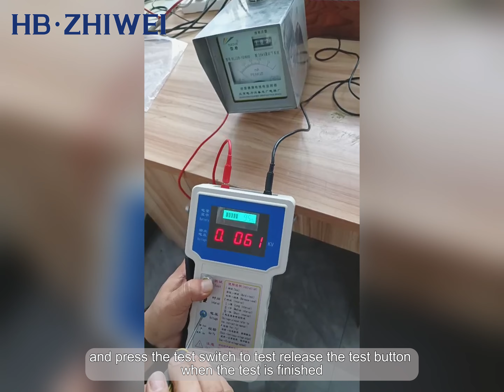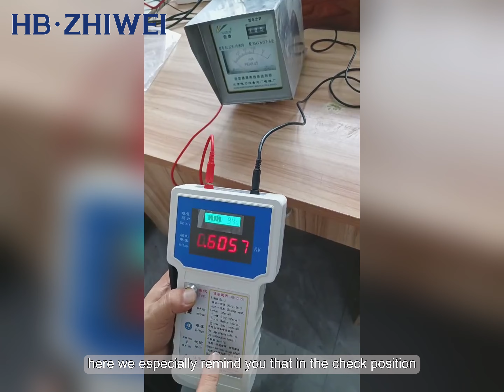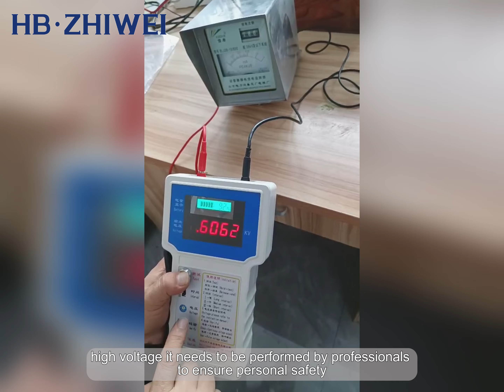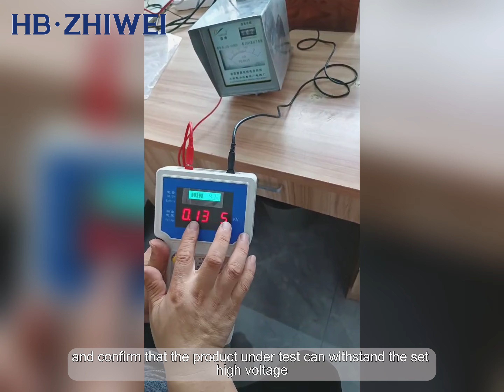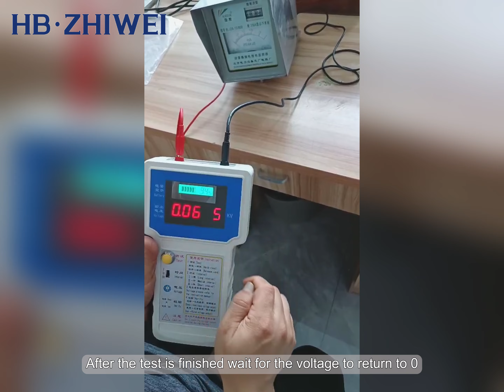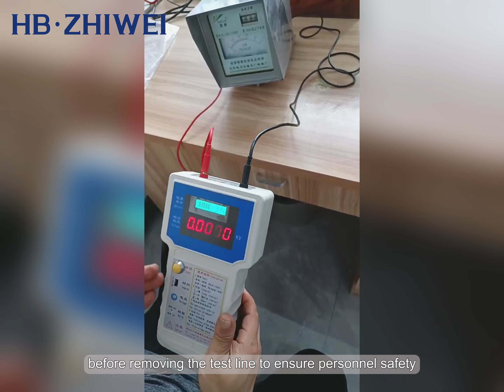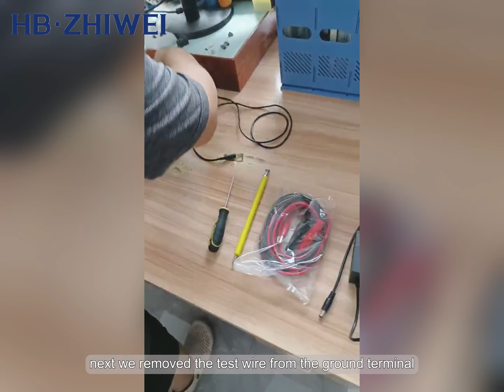Customers can choose the appropriate voltage level for testing according to their test needs. We will not demonstrate them one by one here. Here we especially remind you that in the check position, the instrument will continue to output the set high voltage. It needs to be performed by professionals to ensure personal safety and confirm that the product under test can withstand the set high voltage. After the test is finished, wait for the voltage to return to 0 before removing the test line to ensure personnel safety. Next, we removed the test wire from the ground terminal and performed a demonstration test using a telescopic rod.